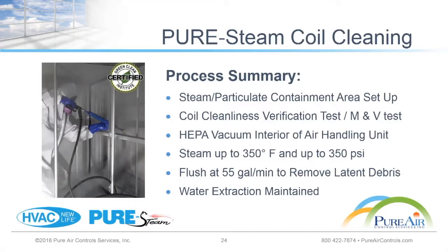Excellent. So that first step process is our steam coil cleaning process. And what's really great about this is that it's a Green Clean Institute certified product. We're using these steam boilers, and I know it kind of looks like a pressure washer, but it is shooting out high temperature and low pressure steam, and that's it. There's water in the boiler, and the steam comes out of the gun tip.